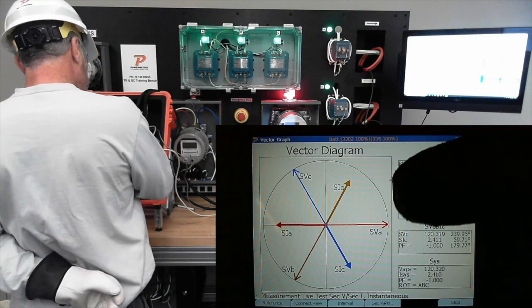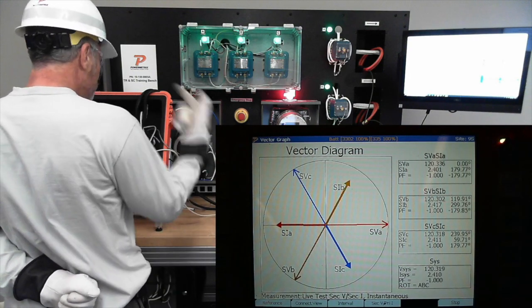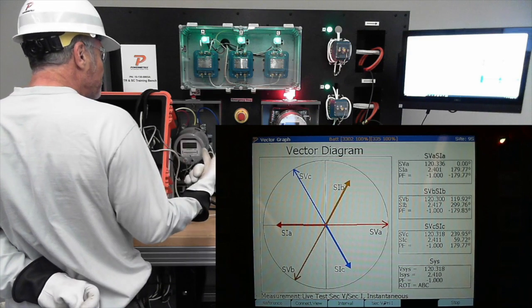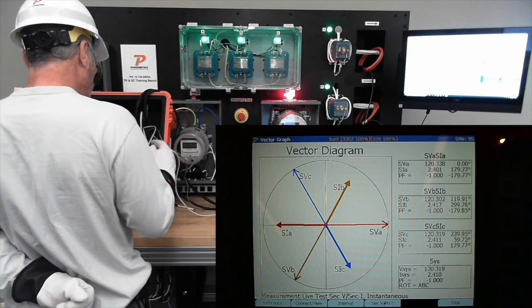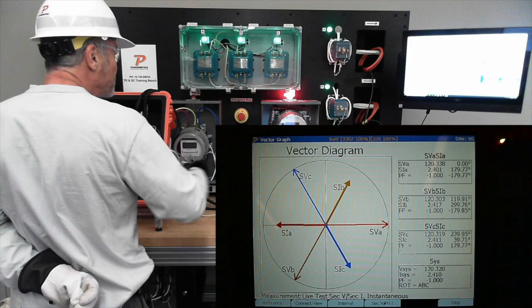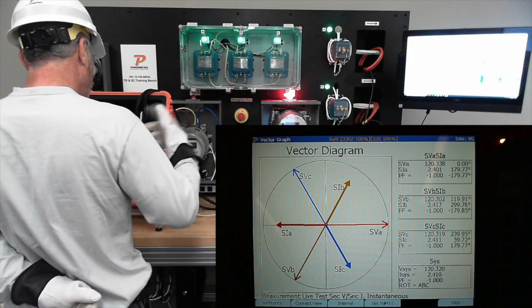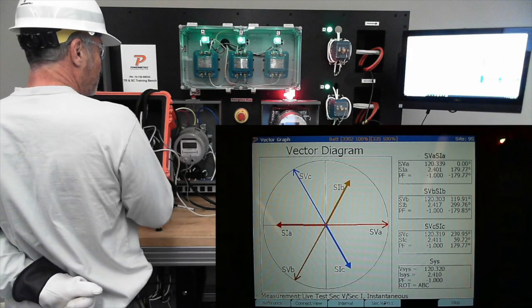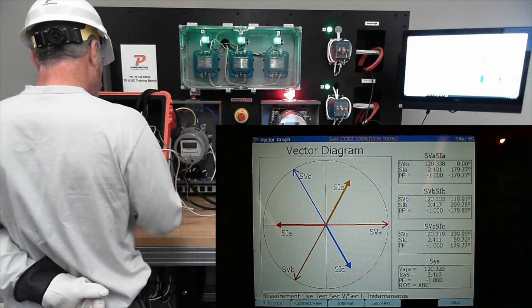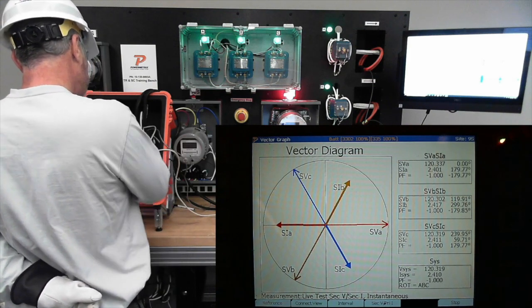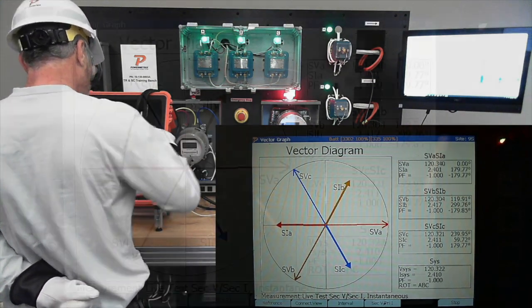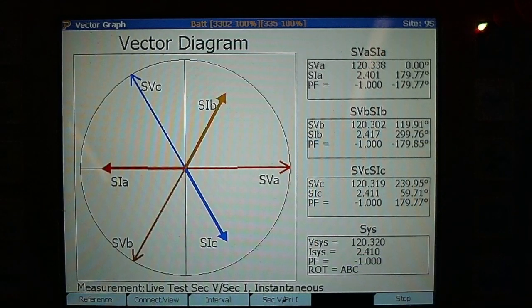But in this case, you're standing at a solar site, so you say to yourself, well, that makes sense. They should all be backwards because clearly now we're in receiving power or generation mode, and I'm set up to look for delivering power to somebody. So when I hook it up, I see all of them showing polarity reversal. And remember, this is the same thing as if we had polarity reversal from just one of the CTs being swapped.